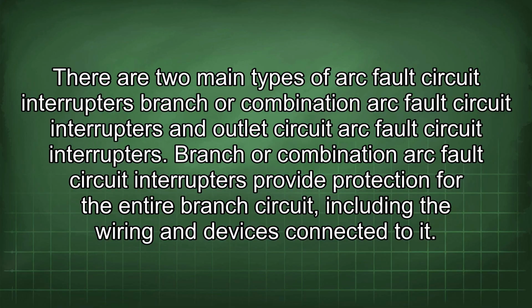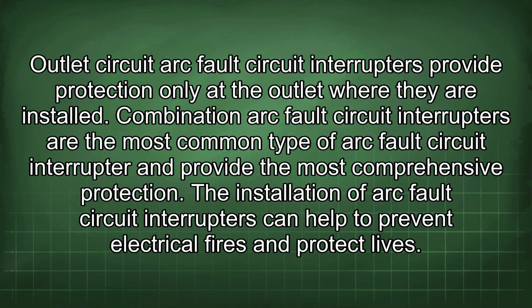Branch or combination arc fault circuit interrupters provide protection for the entire branch circuit, including the wiring and devices connected to it. Outlet circuit arc fault circuit interrupters provide protection only at the outlet where they are installed. Combination arc fault circuit interrupters are the most common type of arc fault circuit interrupter and provide the most comprehensive protection. The installation of arc fault circuit interrupters can help to prevent electrical fires and protect lives.